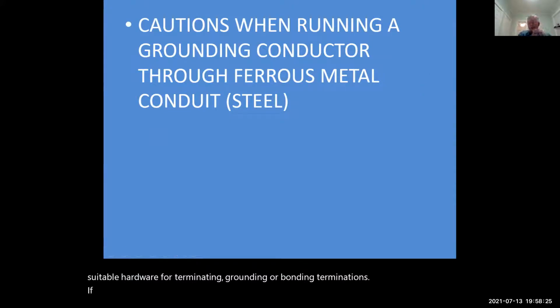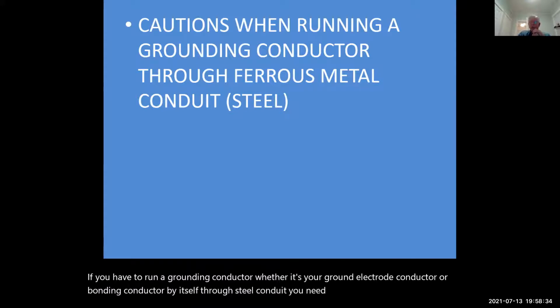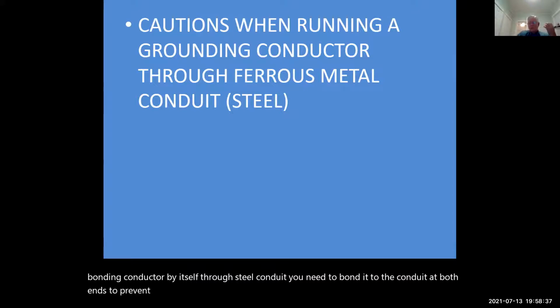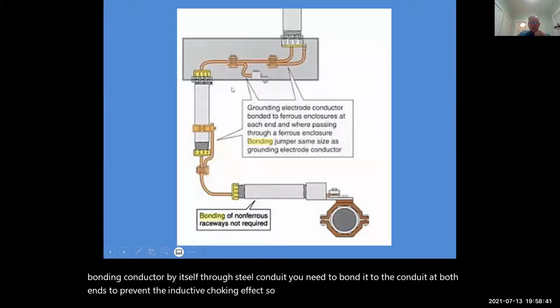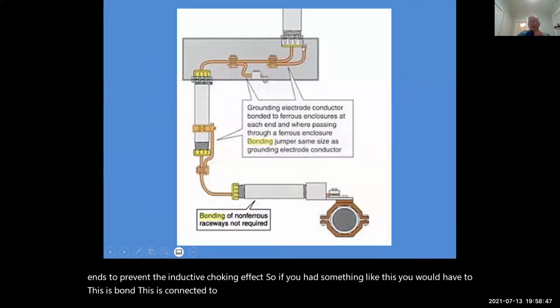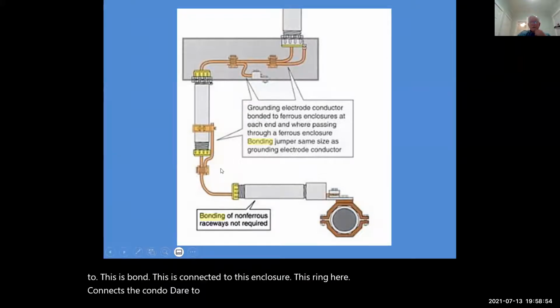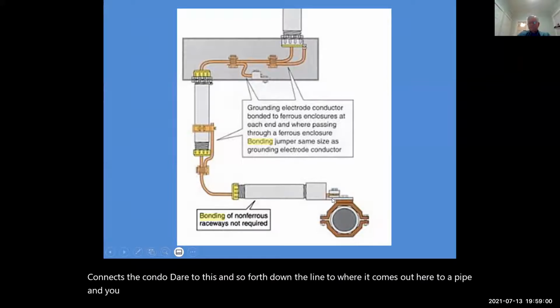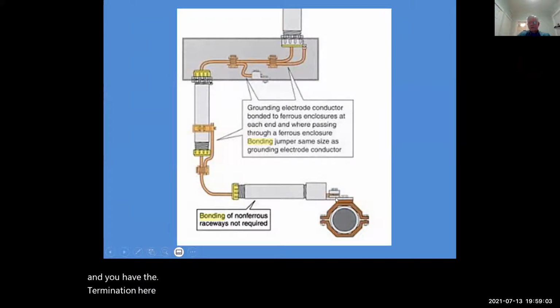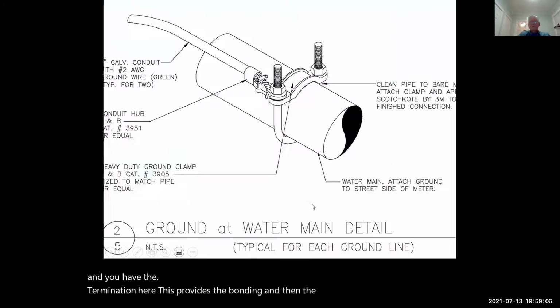If you have to run a grounding conductor, whether it's a grounding electrode conductor or a bonding conductor by itself, through steel conduit, you need to bond it to the conduit at both ends to prevent the inductive choking effect. So if you had something like this, this is connected to this enclosure. This ring here connects the conduit there to this, and so forth down the line to where it comes out here to a pipe, and you have the termination here. This provides the bonding and then the connection to the ground. And a similar kind of arrangement there.